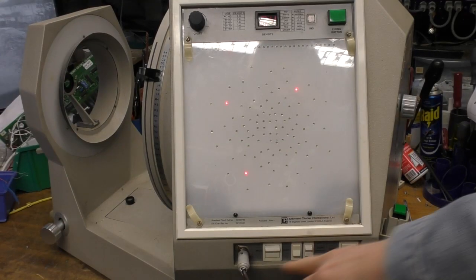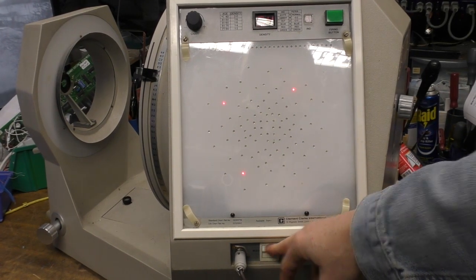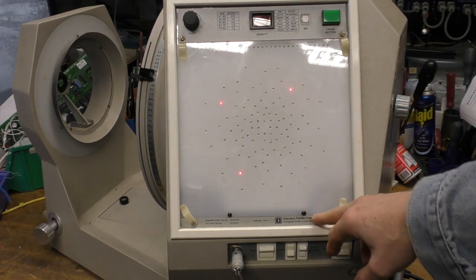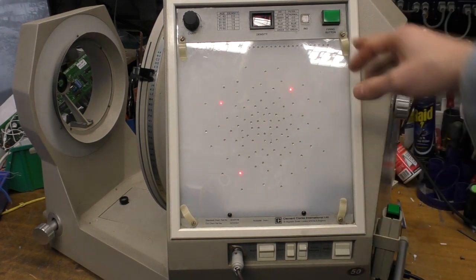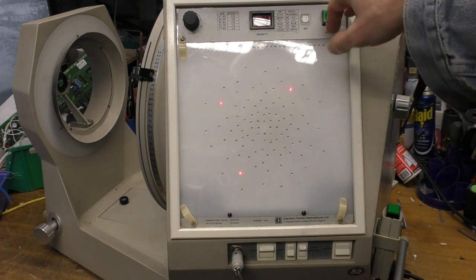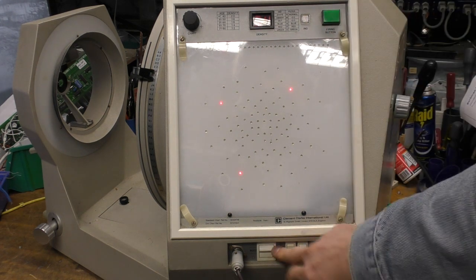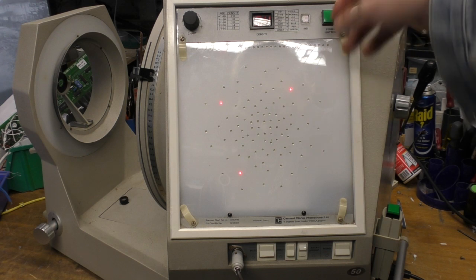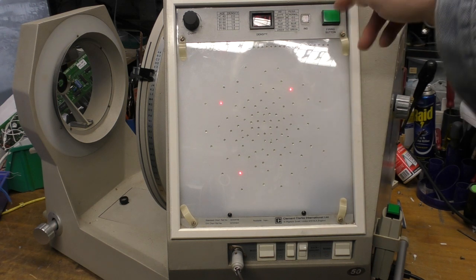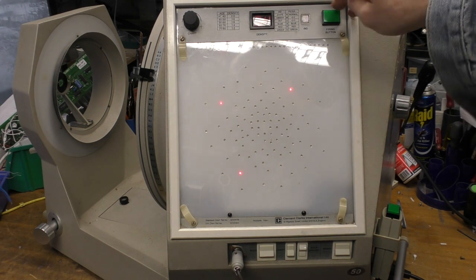There's a few switches on the bottom. One selects the flash mode, so the flash is actually generated by a xenon flash tube, a characteristic pop when that fires. And you can either have it fire immediately when you press the button, or you can have a delay and it fires at the end of a short beep. That's to give a prompt to the patient.